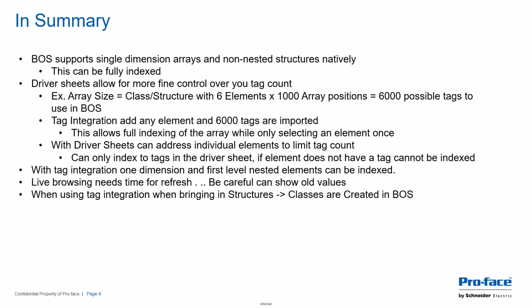So if you're planning a project, and you know you're going to be using Blue Open Studio with its HMI SCADA, it's typically better if you can stick with one-dimension arrays and non-nested structures. That's the best way to make Blue Open Studio more compatible with your system. Hopefully this will change in the future. We're looking forward to it being supported in a better way.